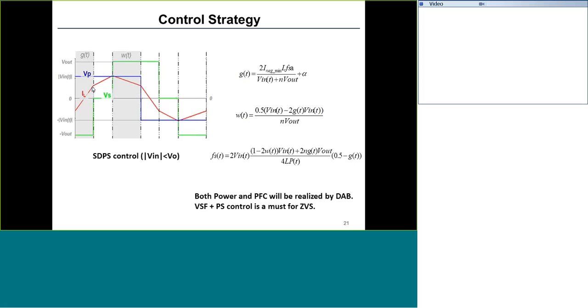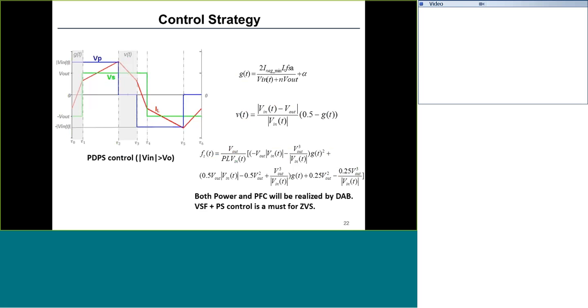We also need to consider the case where the grid voltage is higher than the battery voltage — say the battery is 200 volts but we still have to charge it. In this scenario, we move the extra phase shift to the primary side. The blue line represents the primary side transformer voltage, and now the green line is a 50% duty cycle square waveform, but the blue line, the primary side voltage of the transformer, is turned into 3 levels. Since we introduce an extra phase shift to the primary side, we name this control strategy primary dual phase shift control.